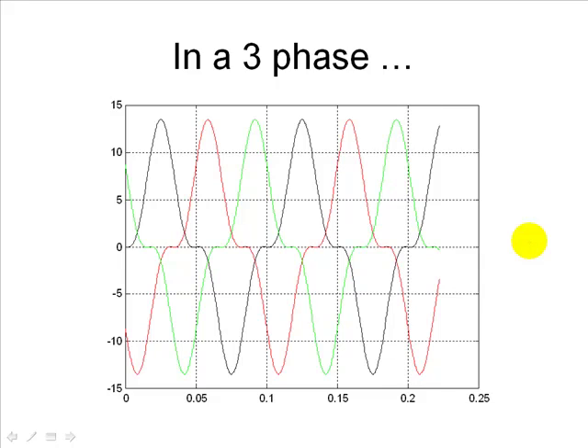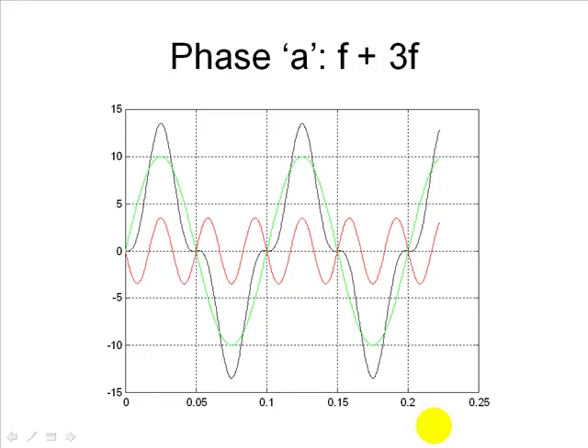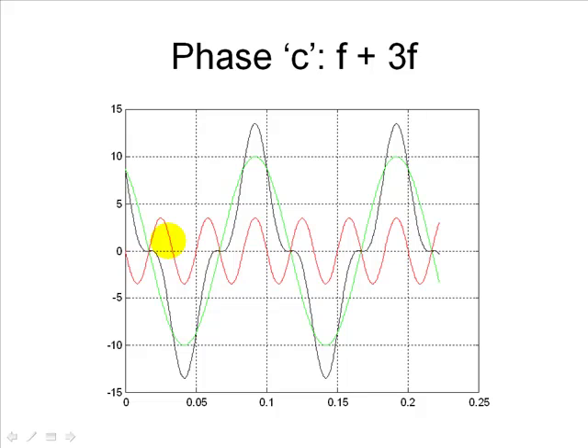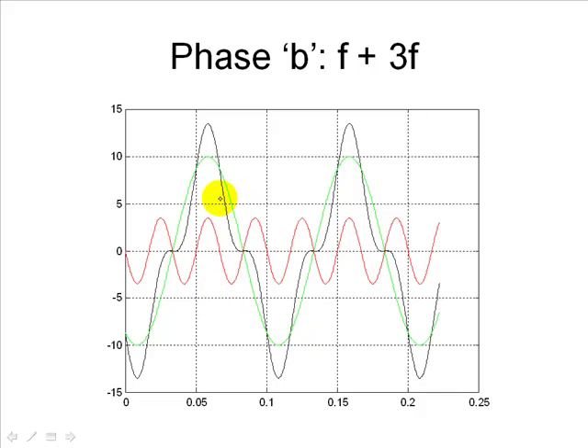In a three-phase system, I have depicted the magnetization current of each one of the phases. In black for phase A, in red for phase B, and in green for phase C. Each one, of course, has a fundamental component and a triple frequency component, but we better see them separately in three different graphics. For phase A, the fundamental component in green and the triple frequency component in red are depicted here, and then for phase B and for phase C. Do you notice the fundamental component of each one of them is actually separated from the fundamental of the previous phase by 120 degrees? Absolutely!